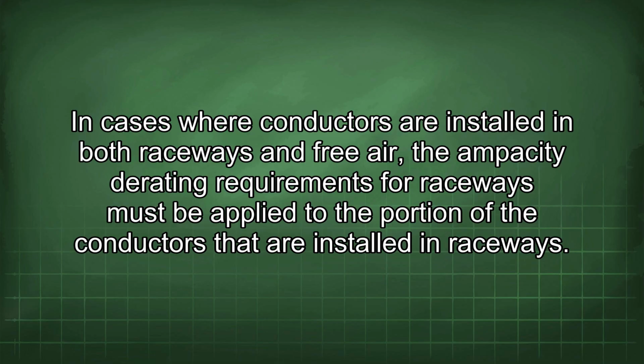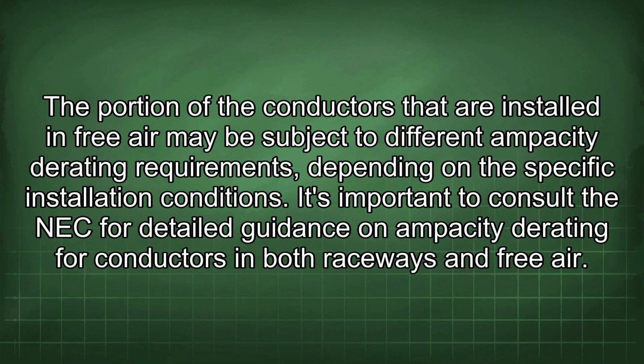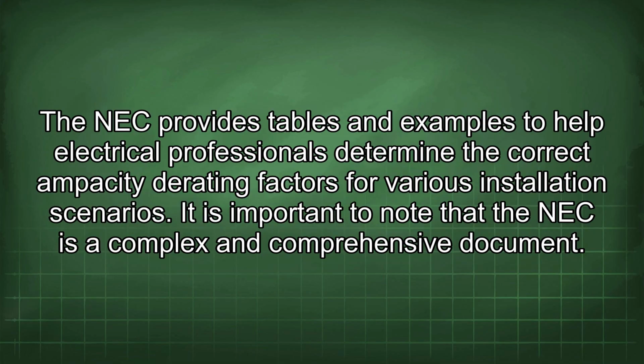In cases where conductors are installed in both raceways and free air, the ampacity adjustment requirements for raceways must be applied to the portion of the conductors that are installed in raceways. The portion of the conductors that are installed in free air may be subject to different ampacity requirements depending on the specific installation conditions. It's important to consult the NEC for detailed guidance on ampacity adjustment for conductors in both raceways and free air. The NEC provides tables and examples to help electrical professionals determine the correct ampacity adjustment factors for various installation scenarios.